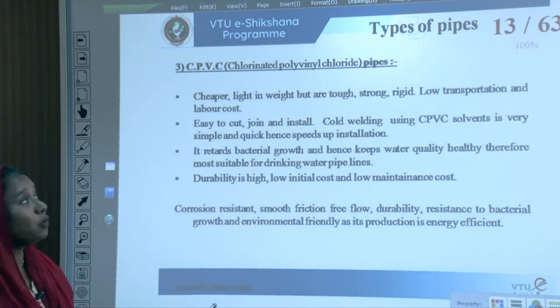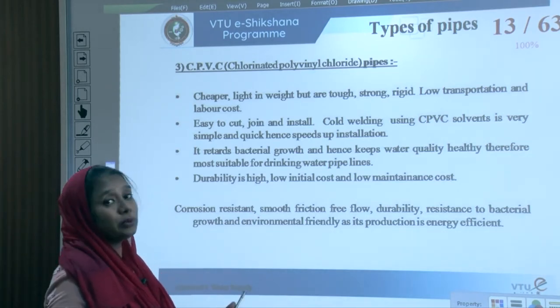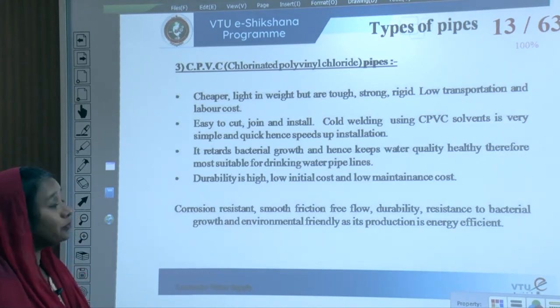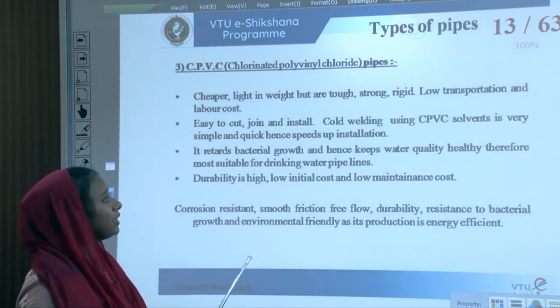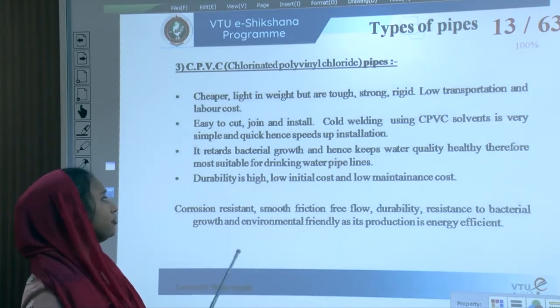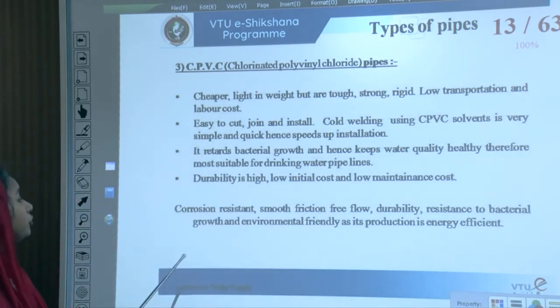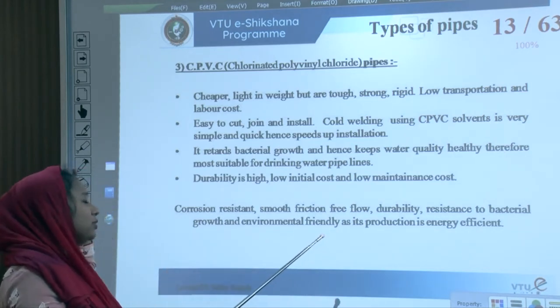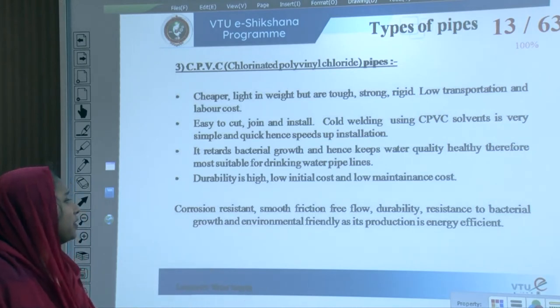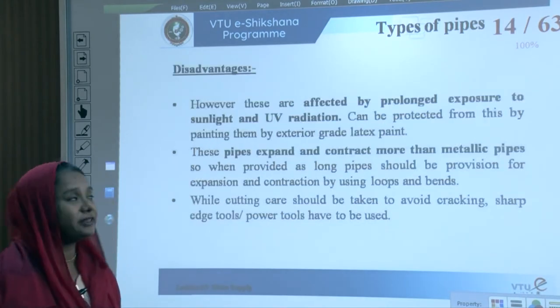CPVC (chlorinated polyvinyl chloride) pipes are cheaper, lighter in weight, and tougher. They are strong and rigid, with lower transportation and labour costs. They are easy to cut, join, and install. CPVC works with cold welding — simple and quick — speeding up installation. It retards bacterial growth, keeping water quality healthy and making it most suitable for drinking purposes. All drinking water pipelines in India are basically CPVC. Durability is high, initial cost is low, and maintenance cost is also low. These pipes are corrosion-resistant and have very smooth friction, making them energy efficient and environmentally friendly.